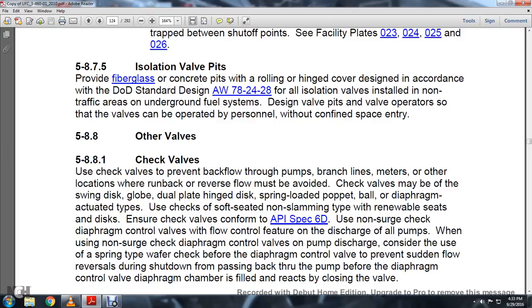5881 check valves. Use check valves to prevent backflow through the pumps, branch lines, meters, and other locations. Reverse flow should be avoided. Check valves may be the swing, disc, globe, double plate hinge disc, spring-loaded poppet, ball, or diaphragm-actuated type. Use soft seat, non-slamming check valves with a renewable seat or disc. Ensure check valves conform to API Spec 6D.